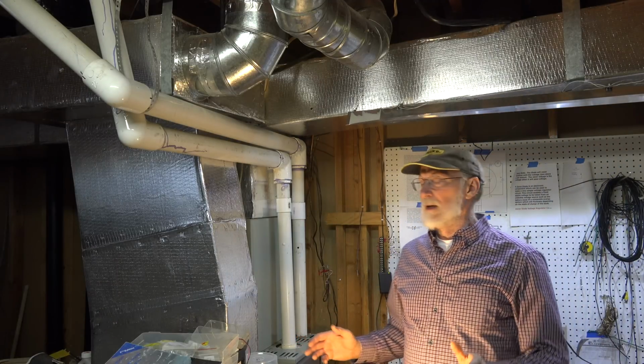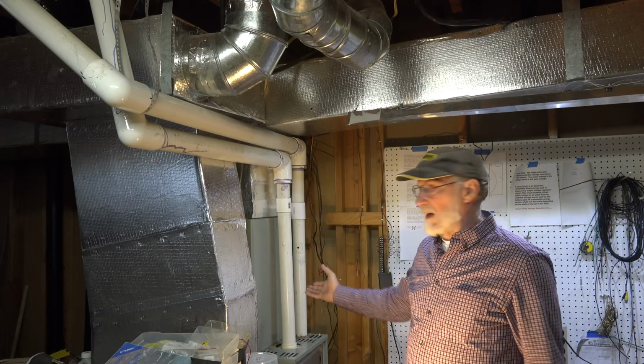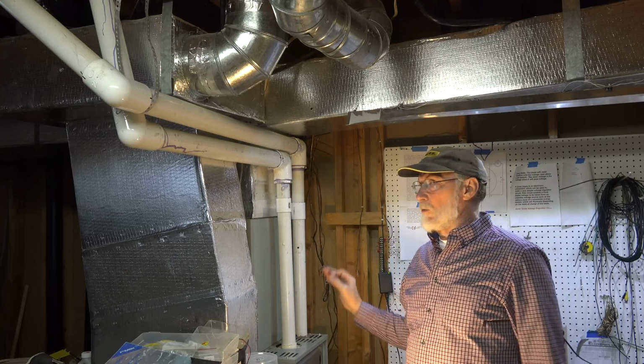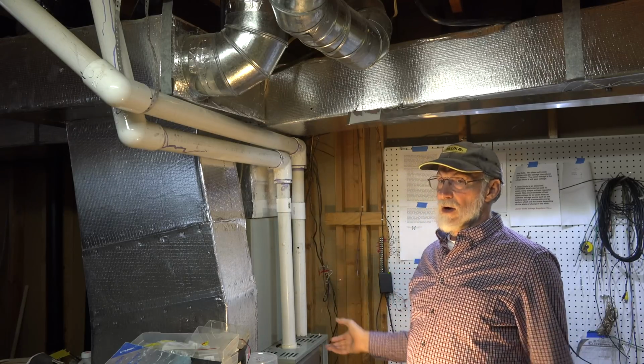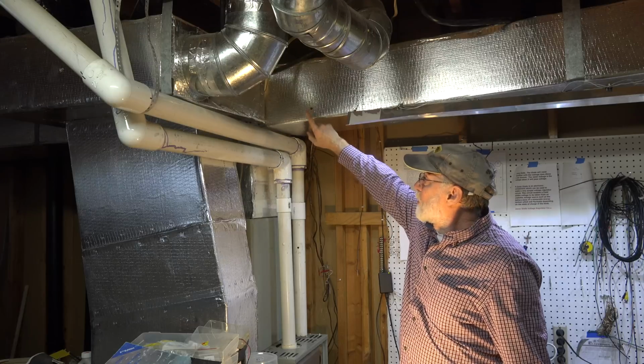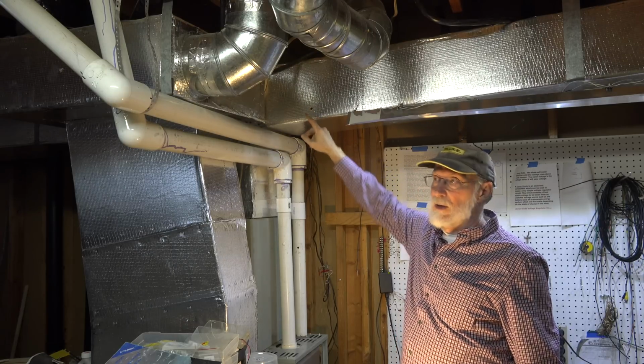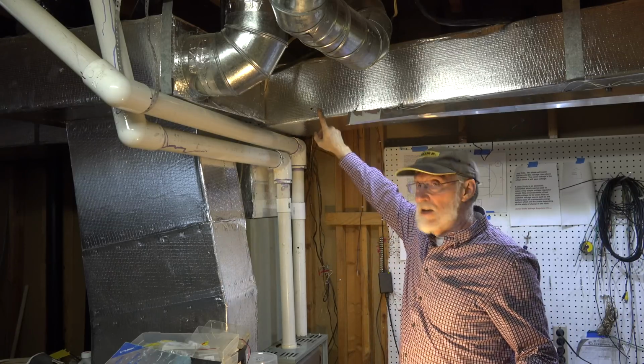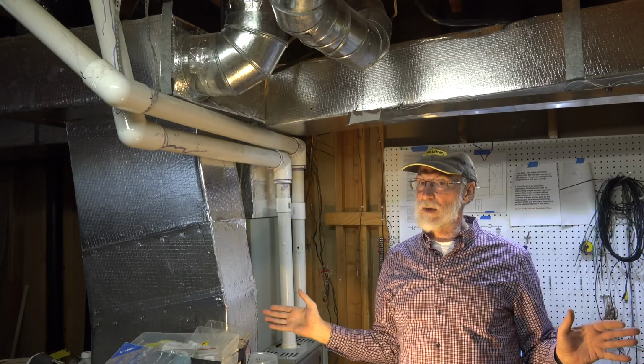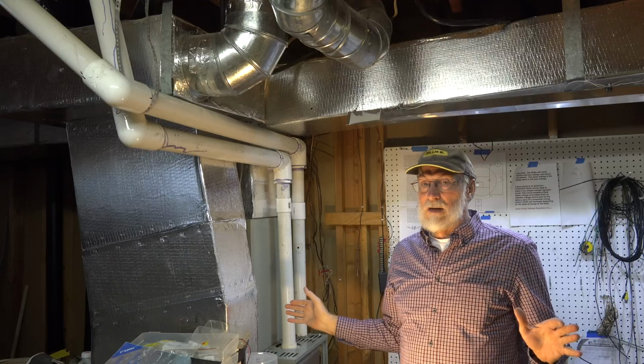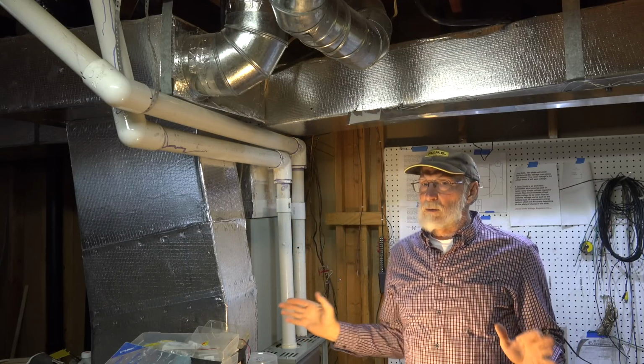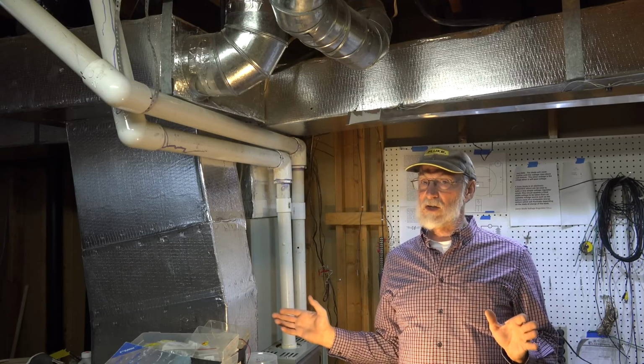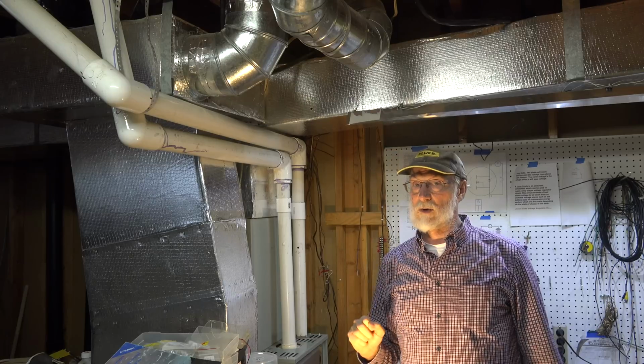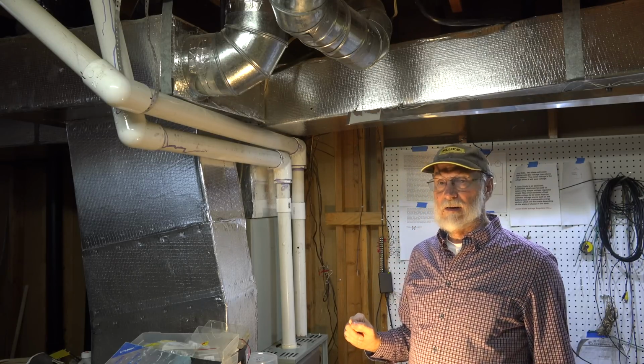But then I'm going to put my probe into the ductwork. First thing I'm going to do is start up the furnace, if it's a furnace I'm looking at and there's ductwork hooked up to it. I want it on high fire. If it's a multiple fire unit, you want it on high fire. Then you can stick a probe in the supply after the fan comes on and see if you have the same amount of CO in the duct as in the structure. That tells you quite a bit, because if it's the same in the structure and the duct, you probably don't have a problem in the furnace. It's very doubtful. If you have an increased concentration in the duct, that's when I start worrying, because that could mean a cracked heat exchanger on a gas appliance.